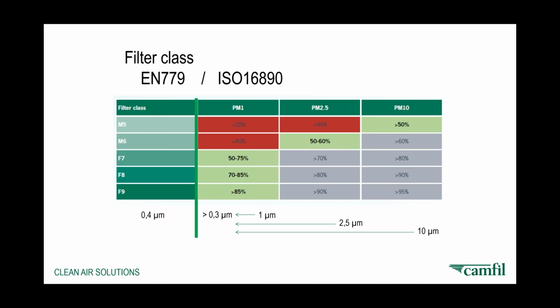PM10 filters are typically coarse, PM2.5 are medium, and PM1 are fine filters. So as you go from a PM10 to a PM1, you're going up the classification or the old class of filters. Again, if anybody wants more information on this, I've done webinars for ASHRAE and some other societies and various universities around the country on this. We have a full slide set available. If you're interested, reach out to myself or Daniel. So that's on the standards of air filters.